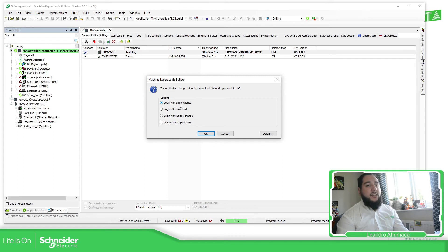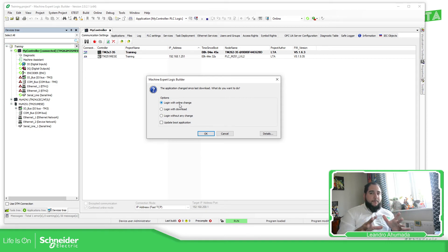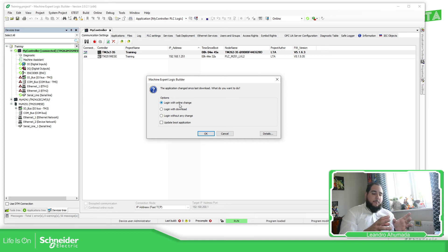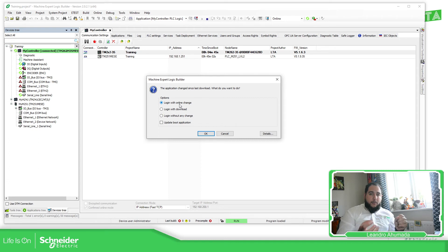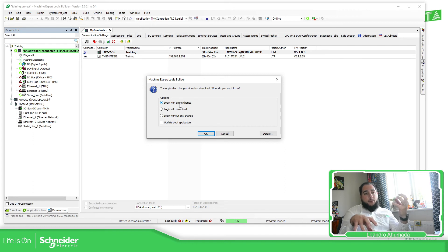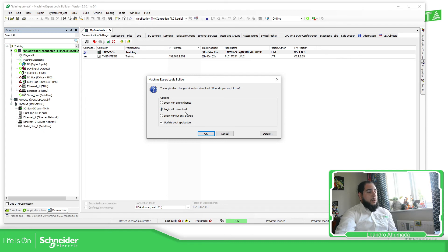We have Login with Online Change, which would only affect one part of the application. In the M262, M241, and M251, we have a RAM and a non-volatile area. If we use Login with Online Change, it will download the application into the RAM. But as soon as we power cycle the equipment, the RAM will be overwritten by the code in the EEPROM or the non-volatile area — which is done with Login with Download, which updates the boot application.